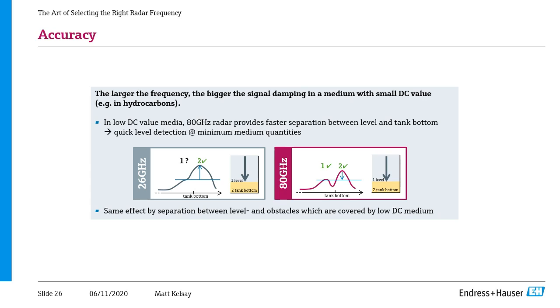What that means is that a radar in that frequency range will read down to maybe about 6 inches, 8 inches to the tank bottom with a low dielectric, but then anything lower than that, and it's just going to lock onto that tank bottom and read 0. So you lose just a little bit of the lower measuring range. If you look on the right though, on a high frequency radar, because that signal is more focused, we get 2 distinguishable peaks even at lower levels in a low dielectric. So again, this allows us to increase our accuracy and increase the usable range of the device, especially down low in the tank.